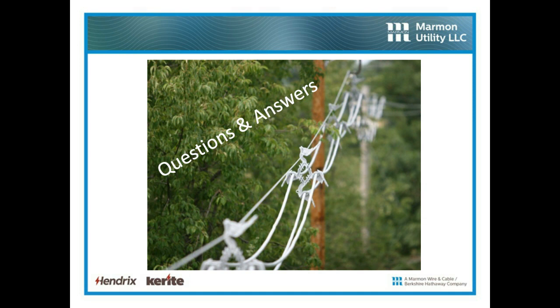Okay, great. Thanks, Brian. Next question, can you talk about how the spacers are typically installed as the conductor is strung or after stringing and tensioning the conductor with a bucket truck? Yeah. We have an installation method called the roll-by method. Basically, you pull in your messenger, you tension the messenger 2,000 pounds at 60 degrees Fahrenheit, and then you pull in your three-phase conductors with roll-by stringing blocks that are spaced evenly every 30 feet. I go and I sag. I dead end those phase conductors at the far end. I go to the payout end. I sag the conductors such that I have 6 inches of phase conductor sag every 30 feet.